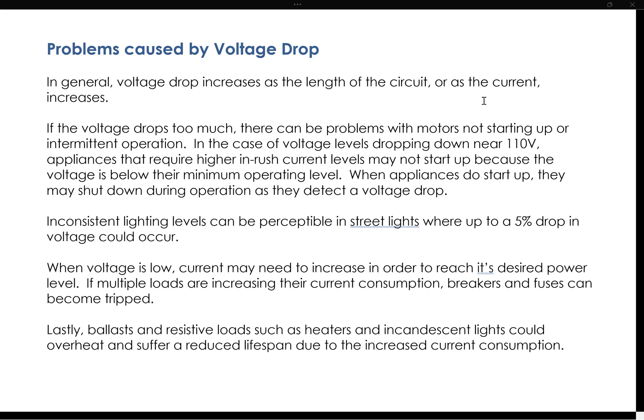Sometimes when appliances do start up and there's a voltage drop issue, they will shut down during operation because they have a way of detecting that voltage drop, and then the appliance shuts off. This causes issues that are hard to diagnose. It can even be apparent in inconsistent lighting levels — for example, with long street lights, where up to a 5% drop in voltage can occur, and that's actually perceptible to the human eye.